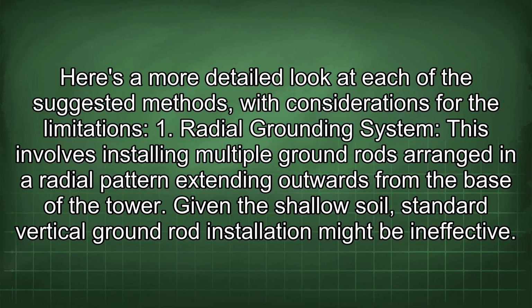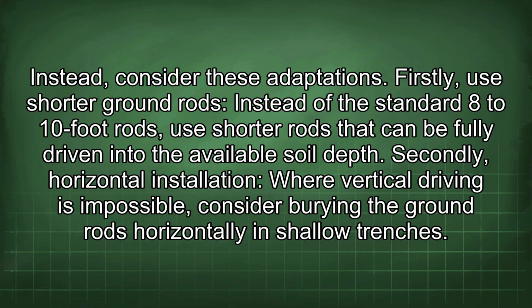This involves installing multiple ground rods arranged in a radial pattern extending outwards from the base of the tower. Given the shallow soil, standard vertical ground rod installation might be ineffective. Instead, consider these adaptations. Firstly, use shorter ground rods. Instead of the standard 8 to 10 foot rods, use shorter rods that can be fully driven into the available soil depth. Secondly, horizontal installation.